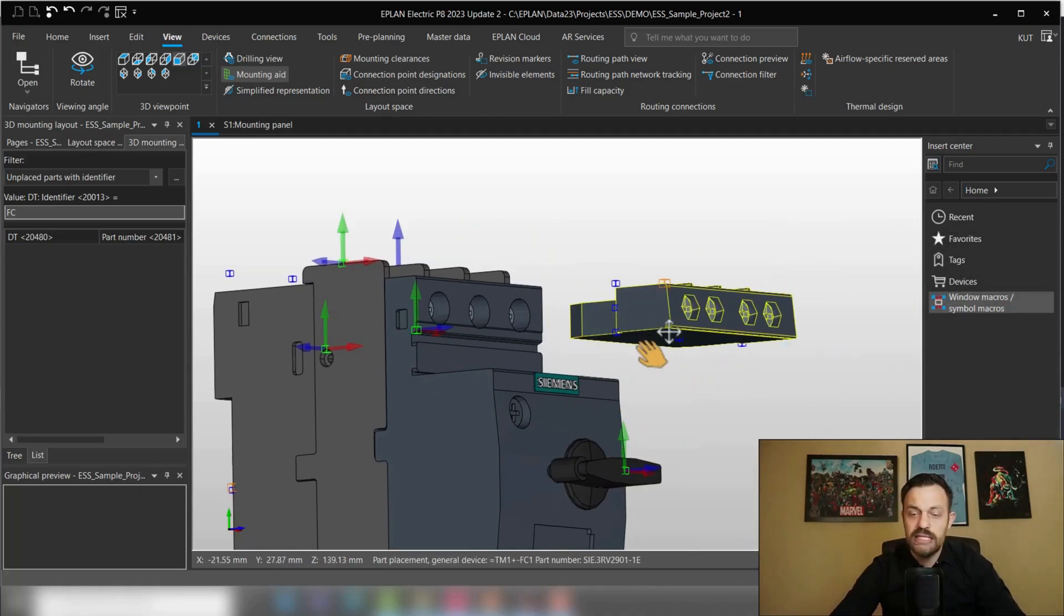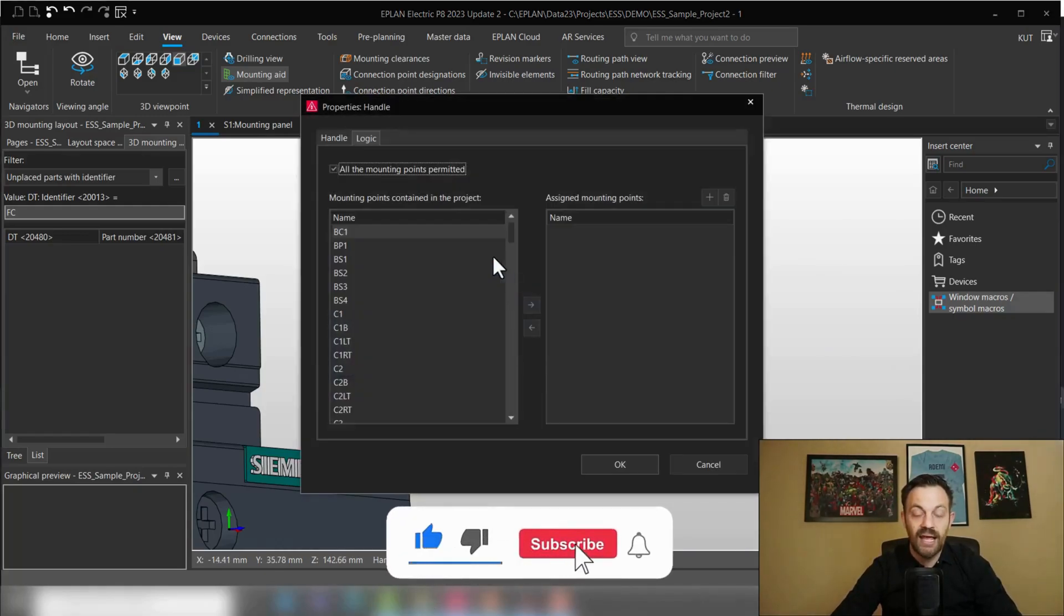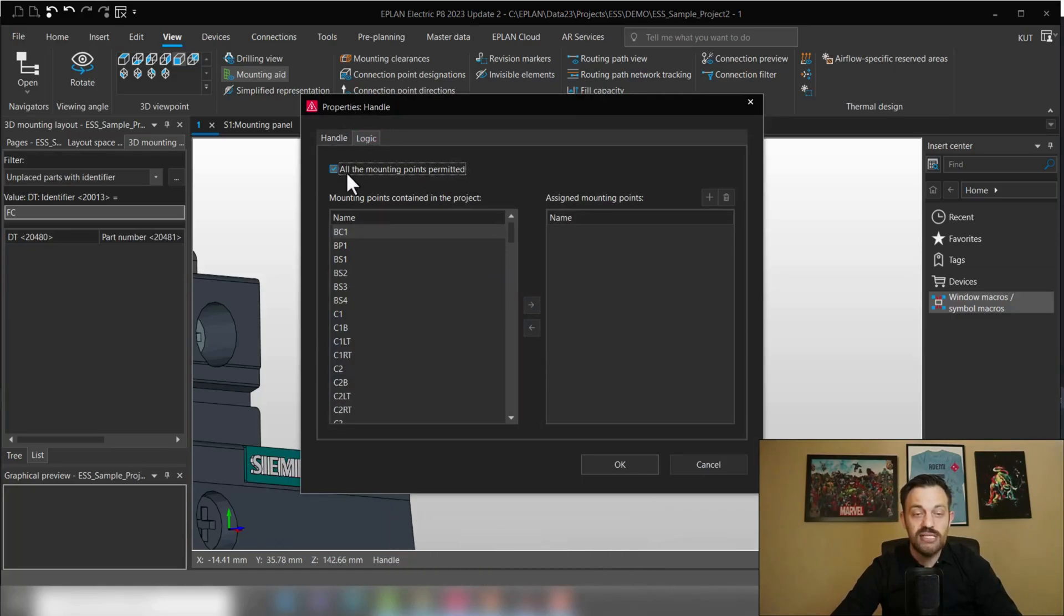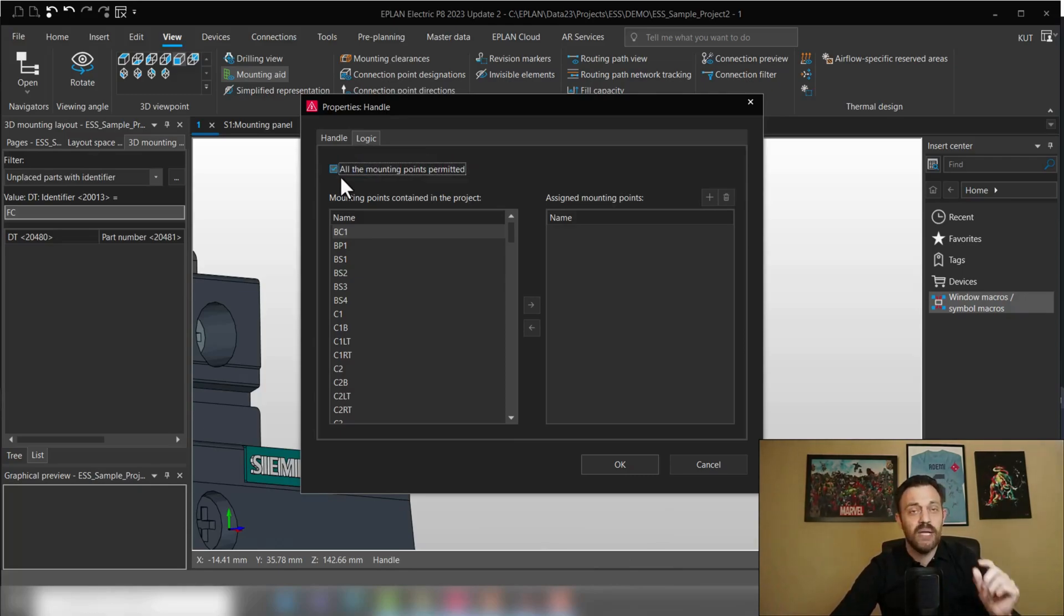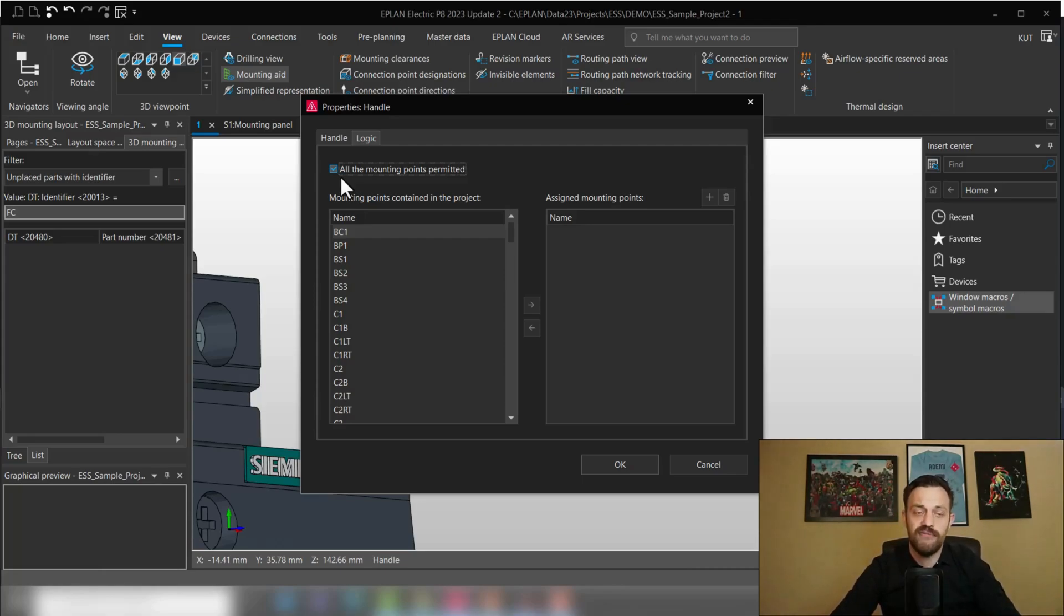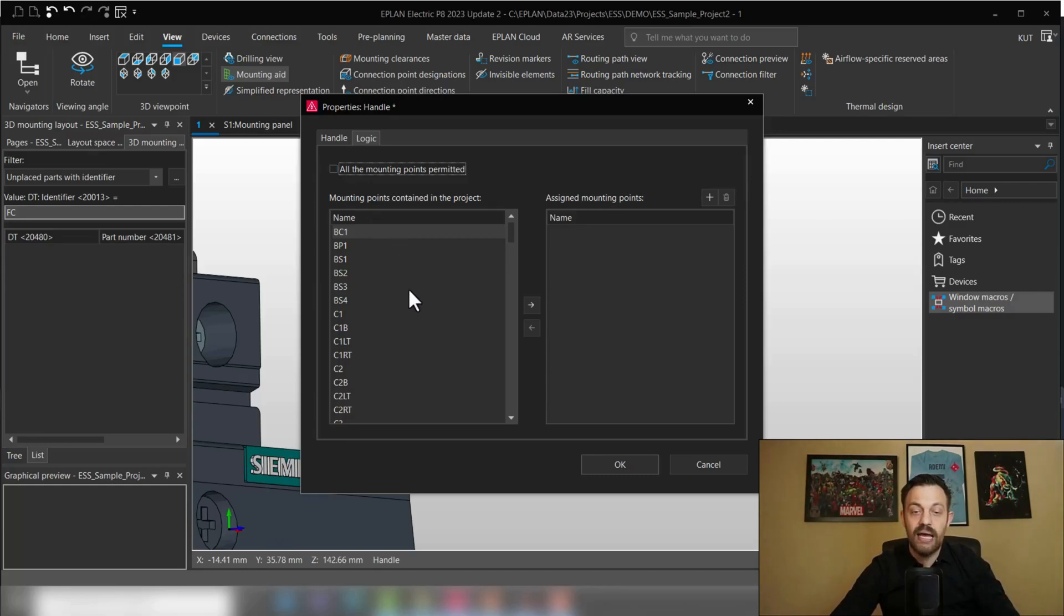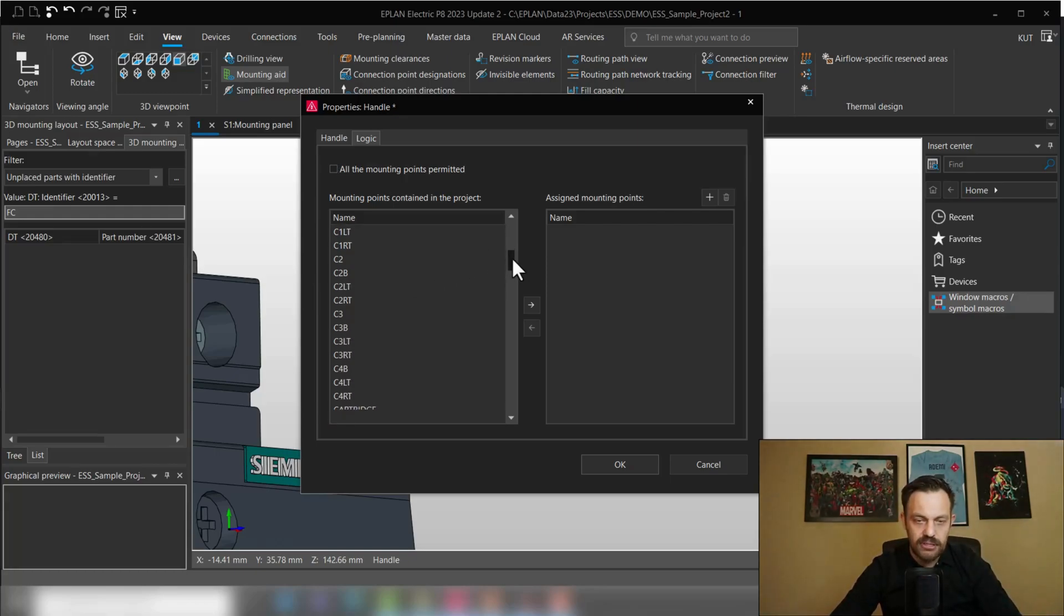For this, when you create a macro of the auxiliary switch, you need to select the handle point. The second tab is logic, and here you see the default setting is all the mounting points permitted. That means you are defining that the handle can be attracted to all mounting points, as you saw what I just did before. If you now deactivate this and select only the one point which you would like to use, then we will see what happens afterwards.